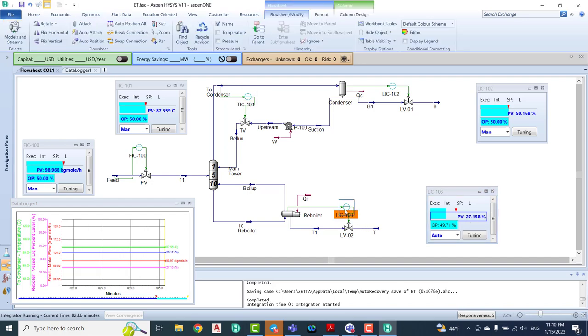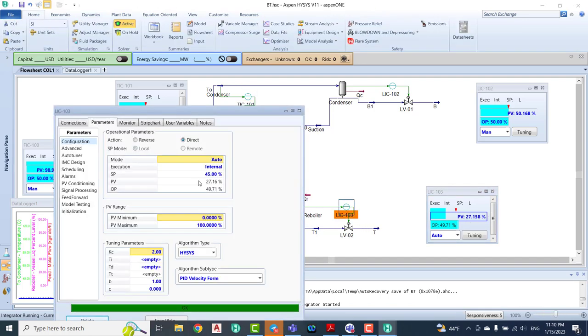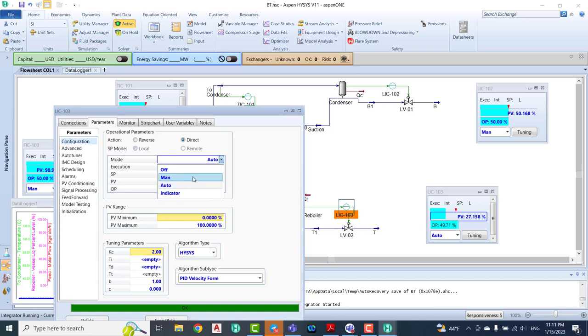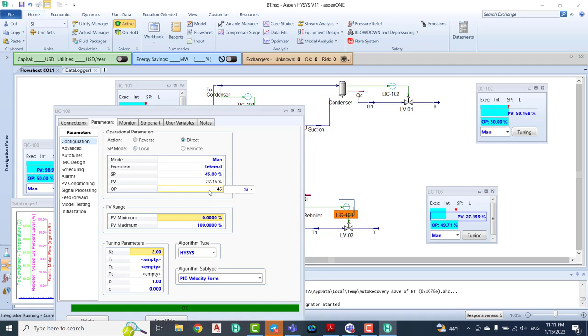I can go to the inside LV. Let's see, the setpoint is 45, the PV we have is 27. You should click in the auto to increase the level again. I can change to the manual. I now change to the manual to reduce the output percentage from, for example, 49 to 45.